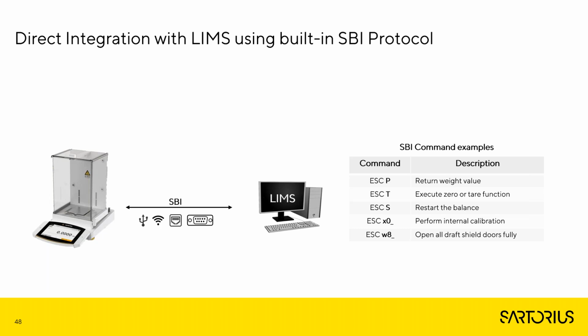We have a couple of them. This is the Sartorius balance interface protocol, and it is supported. You can connect using Ethernet cable, wireless, USB, or serial connection. It's a bidirectional protocol, and the external system, for example a LIMS, can control the balance. It can send a command such as return the weight value, execute the tare function, restart the balance, etc.